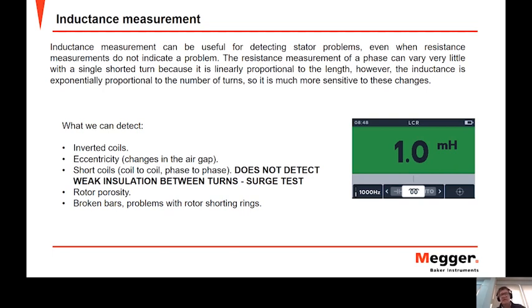And with inductance, we can detect such things as inverted coils or reversed connections, reversed phases, eccentricity, and short circuits, as we've already said. But let's be clear, this is a welded short circuit within a phase or even between phases. It's not detecting weak insulation between the turns. That's where we need the surge test, which is another discussion completely. We can also see rotor porosity and broken bars, for example, using inductance.